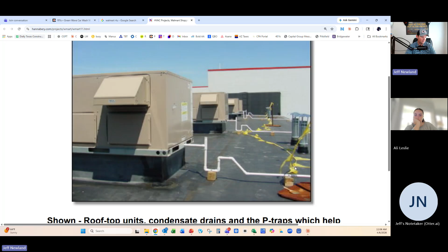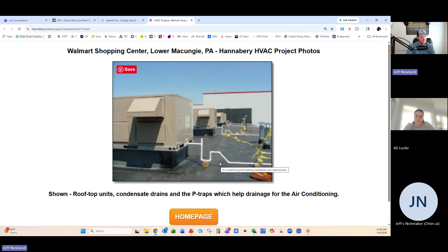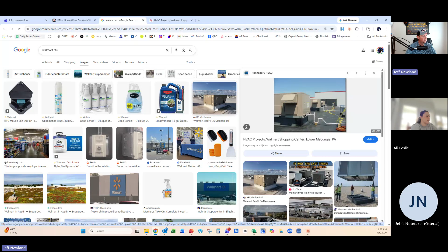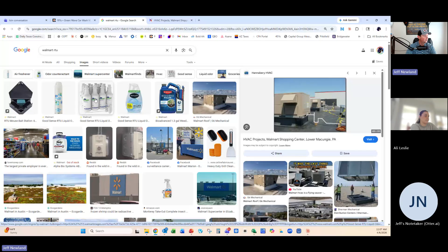When you're running HVAC on a roof, or running anything on the roof, you have to make sure it doesn't sit directly on the roof itself. There's either a stanchion that's used — they make them specifically for gas lines, PVC pipe, duct work, whatever — but it elevates it up off the roof surface. You never run anything actually touching the roof, because there has to be some way to secure it, and you don't want to secure it through your roof membrane.